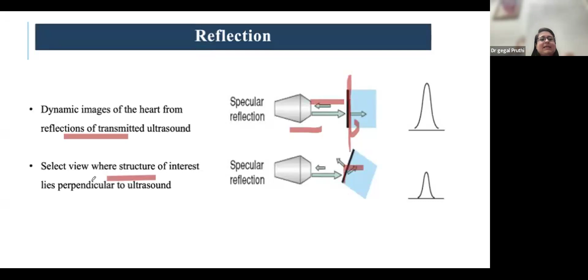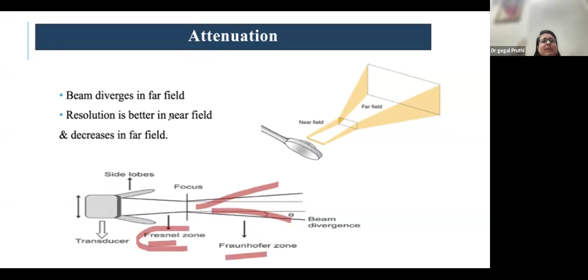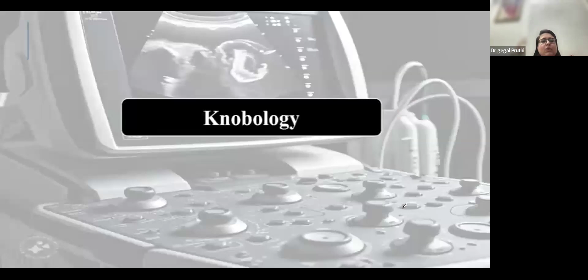So now coming to the attenuation. Attenuation is loss of intensity and it is due to the beam dispersion in the far field or due to the absorption in the form of heat. So as we know, there are two types of zone, that is near field and the far field. Near field is known as the Fresnel zone and far field is known as the Fraunhofer zone. Resolution is better in near field and decreases in the far field.